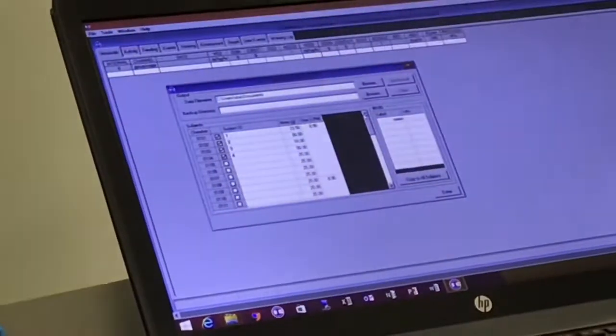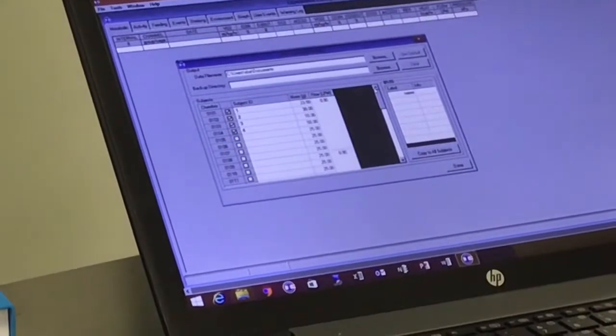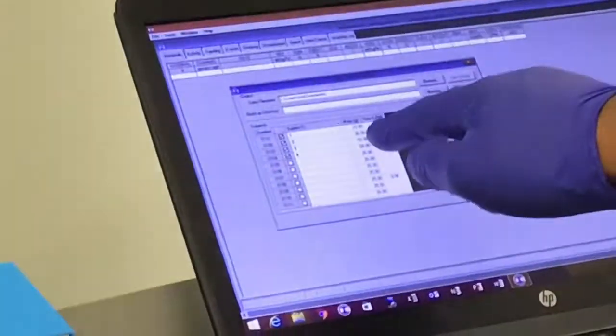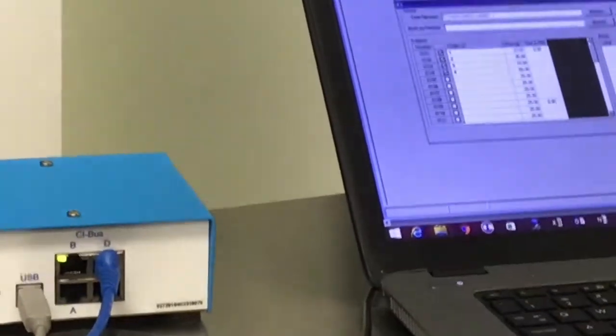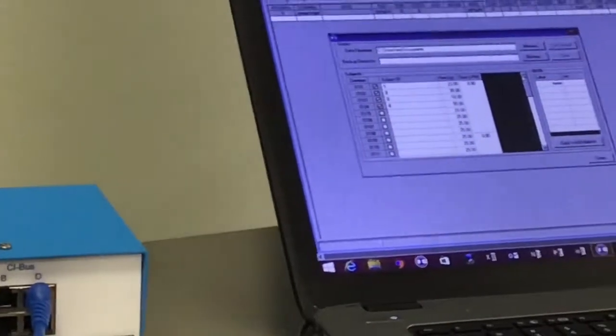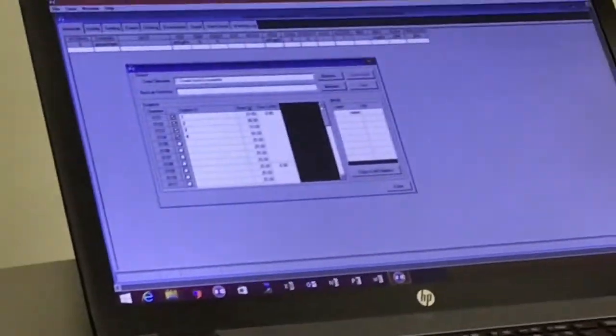So right now it's set at 0.9, but guess what? If you have very tiny animals, what will happen to your deltas? They will be very small. You can decrease the air to get your deltas within that range. That's what this flow is for. The only thing is, since there's only one pump sucking all 8, it's the same flow everywhere, unless we had different restrictors, and that's not how we do it. You have the same size restrictors everywhere.